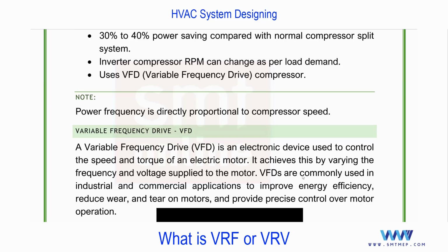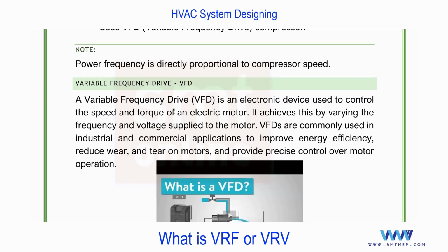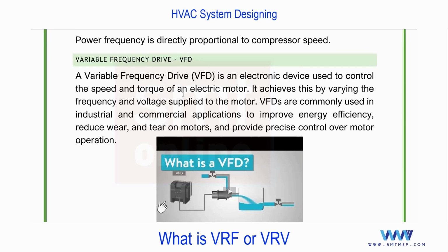The same concept is applicable for pump and fan. Why am I adding pump and fan? Because you'll find this same VFD concept at the time of pump selection as well as fan selection. If you talk about the secondary pump, it is a variable speed pump. Even in a VAV system, the fan motors are variable speed drives, that is, with a VFD drive. So this concept is important. A variable frequency drive, VFD, is an electronic device used to control the speed and torque of an electric motor. This can be achieved by varying the frequency and voltage supplied to the motor. VFDs are commonly used in industrial and commercial applications to improve energy efficiency, now in the market in HVAC and plumbing, not commonly in firefighting, because in firefighting we are not talking about running cost. In plumbing also you'll find this concept for pumps to save energy.